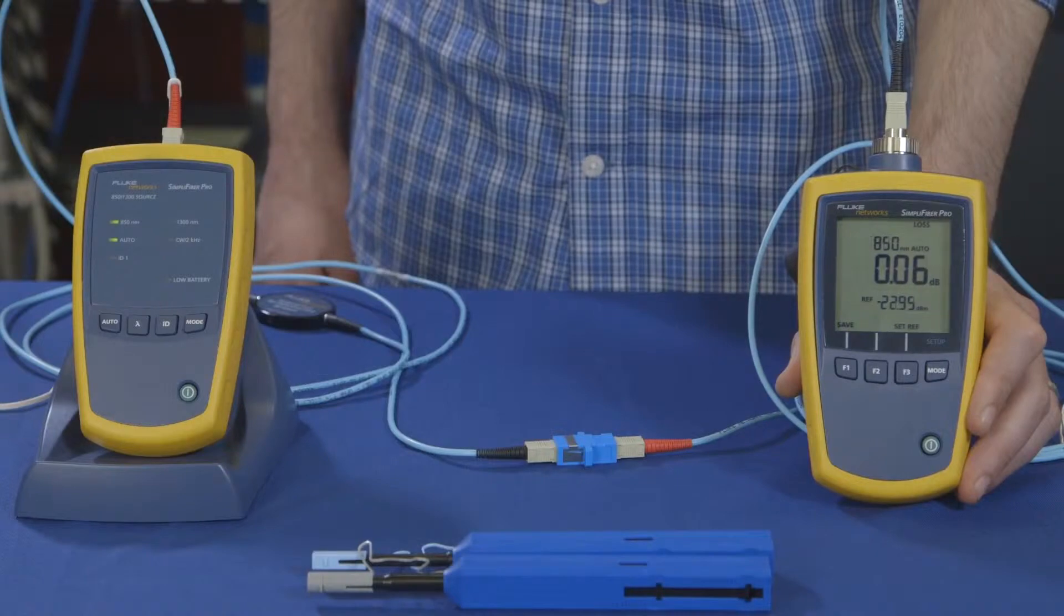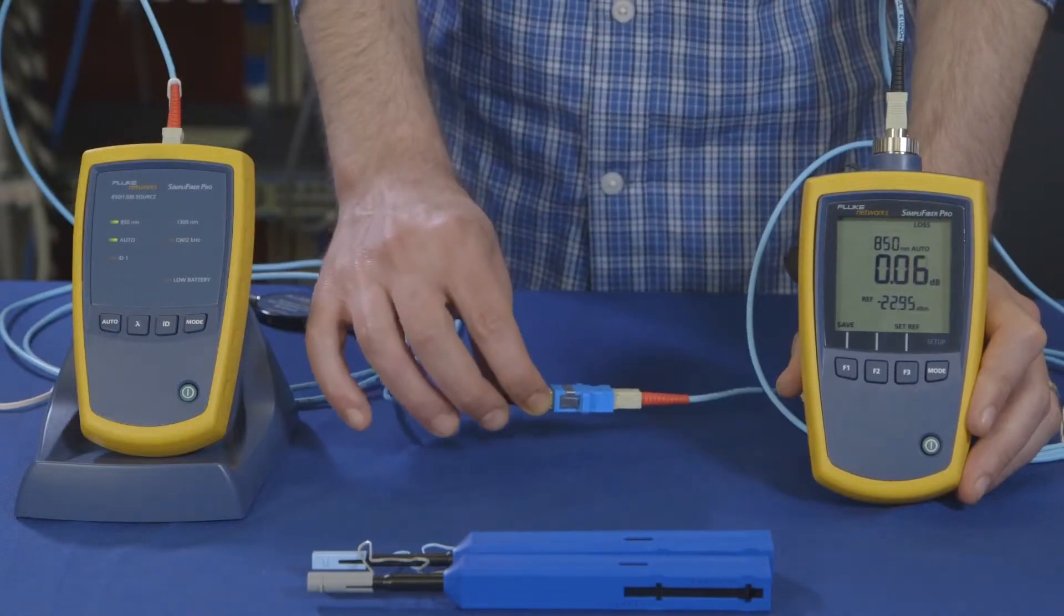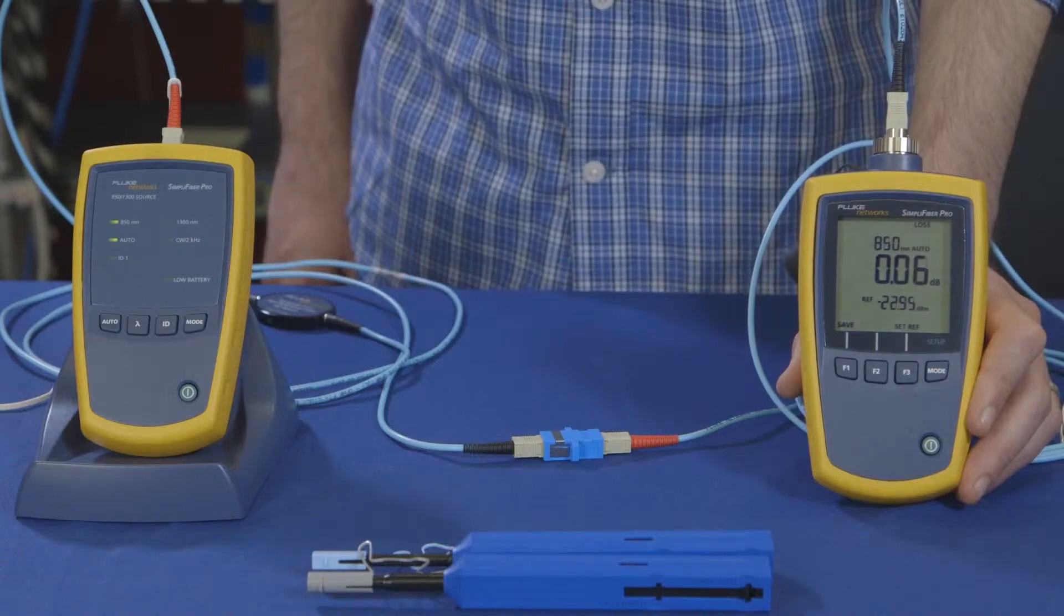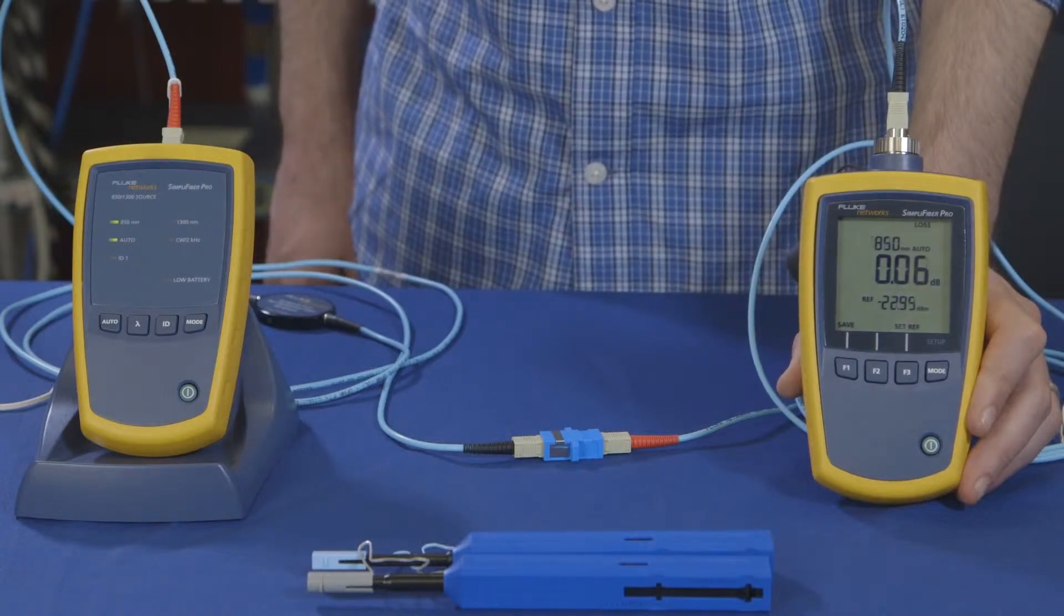Using a coupler, we've attached the second TRC, and we'll run a test to verify they're good. We should not get a loss greater than 0.15 dB.